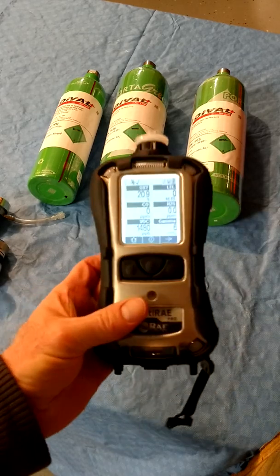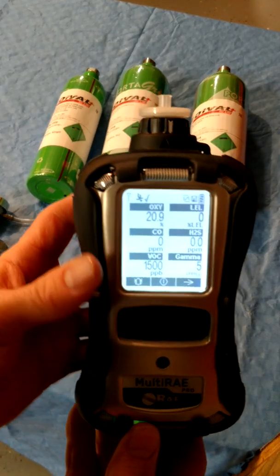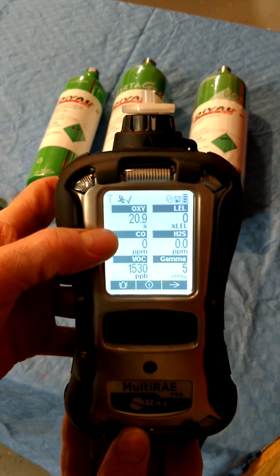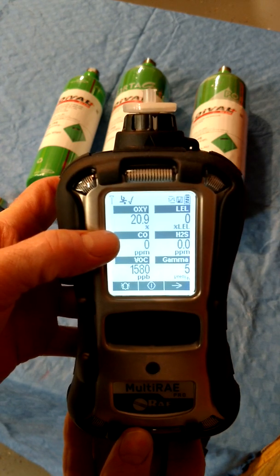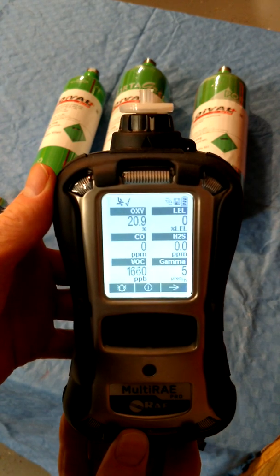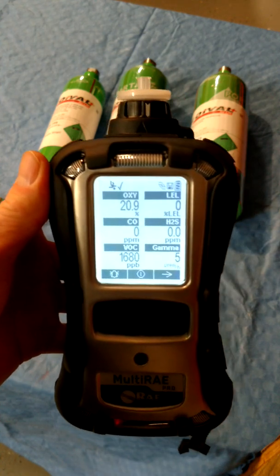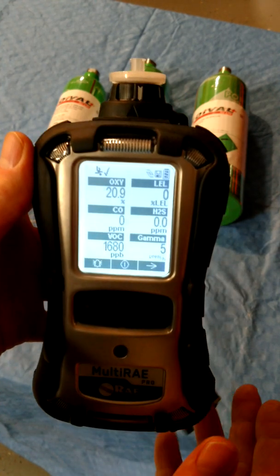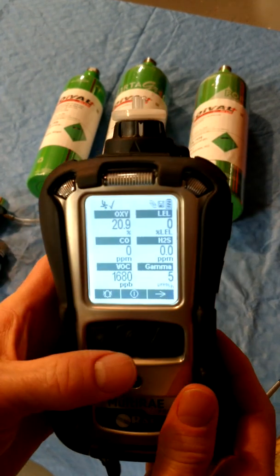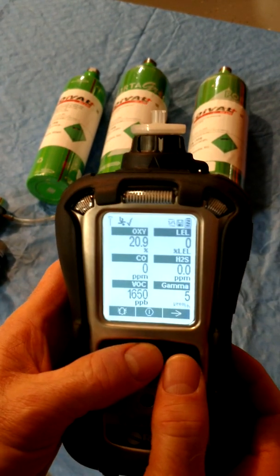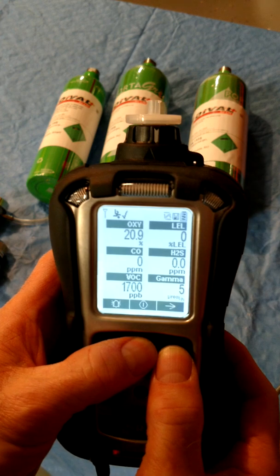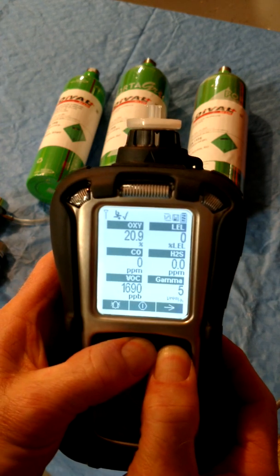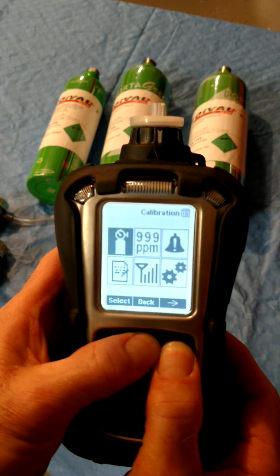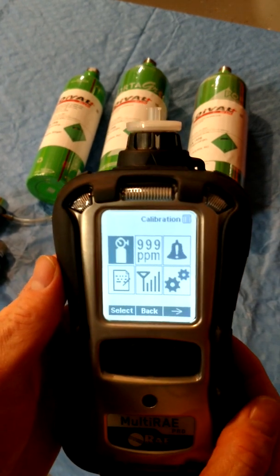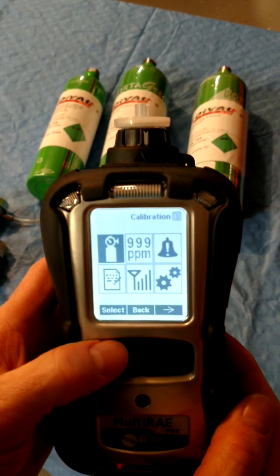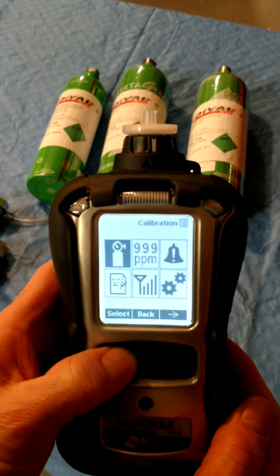On the meter, if you see a solid gas bottle icon next to any sensor, that is also an indication that calibration is needed. To get to the calibration menu with the meter set up in the advanced program mode, press the mode and the N keys simultaneously. The programming menu shows up. Press select to get to the calibration menu.